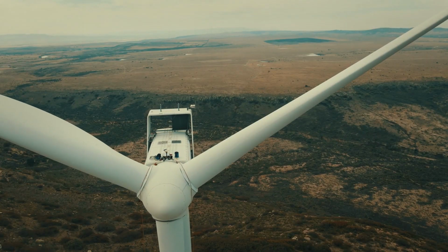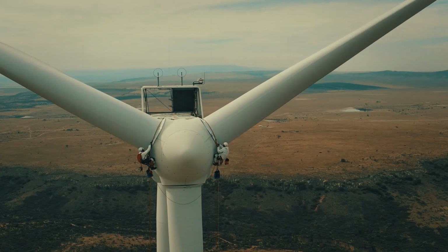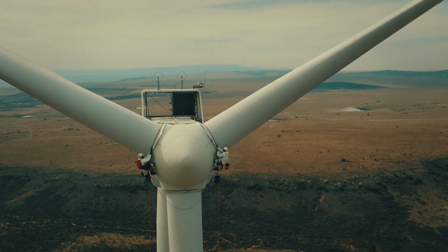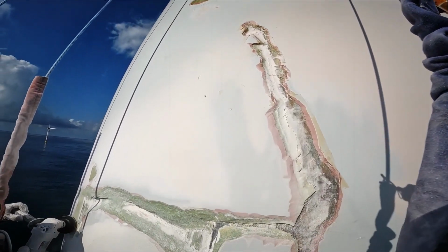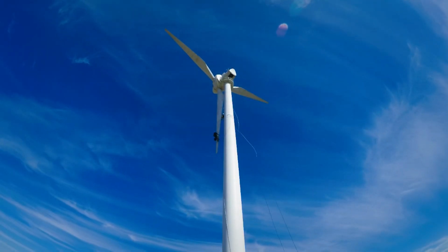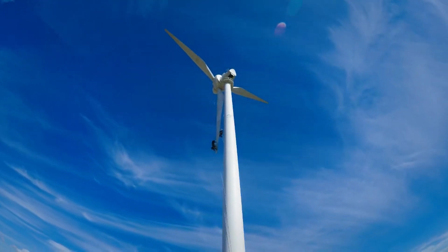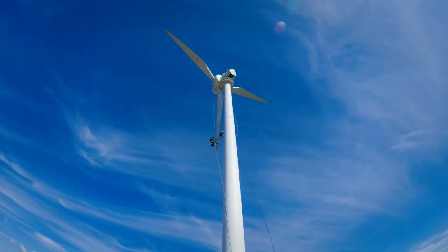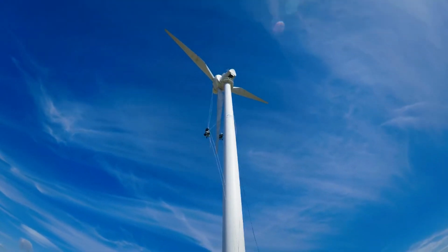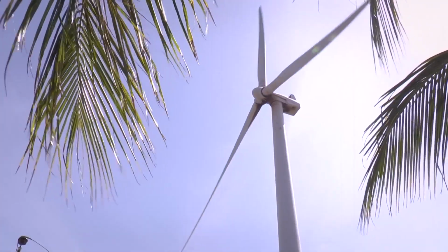The first step is to do a visual check. It is important to examine the leading and trailing edges in great detail. To identify microcracks that are not apparent to the naked eye, use dye-penetrant testing or ultraviolet testing. Remember, the parts closest to the root and the tip experience the most stress.